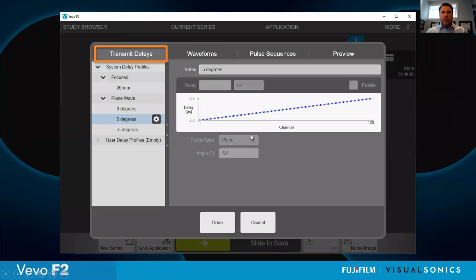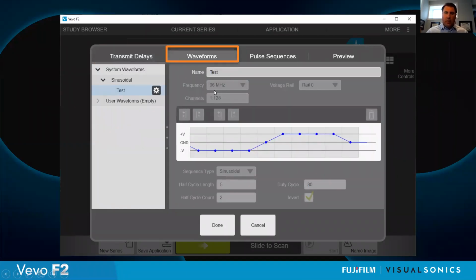So how does this all come together? This is the user interface that I had mentioned earlier. Here we're looking at the transmit delay panel, what we're looking at is a 5-degree steered plane wave. So we can see there's no focus pattern. The time delays here are really just set up to give that 5-degree angling of the transmit profile. We could also set up something similar. You can see examples, focused beams as well, and that allows us to really set up particular transmit delays that we desire. We can then start to program in waveforms. Here we just see a simple single cycle pulse, but there's lots of flexibility in terms of how long the pulse you would like it to be, the polarity, whether you'd like to invert the pulse, the amplitude.